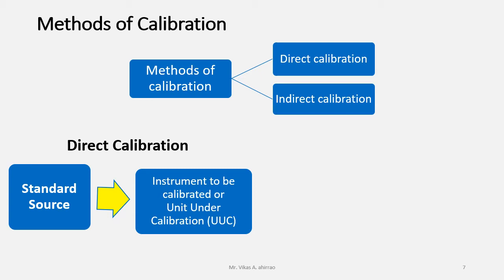For example, if we want to calibrate a DC voltmeter, we may use a standard DC power supply as a source whose accuracy, precision, as well as uncertainty is known to us, and that will supply standard inputs in terms of the voltages to the DC voltmeter, and then we can calibrate that meter against the standard source.